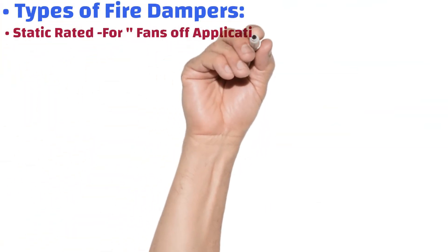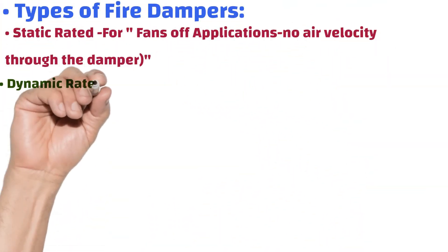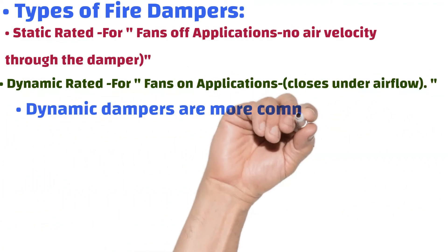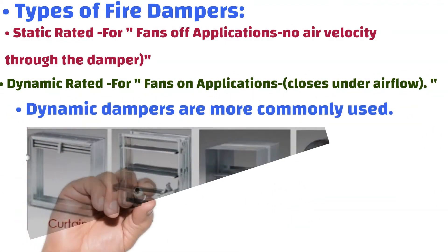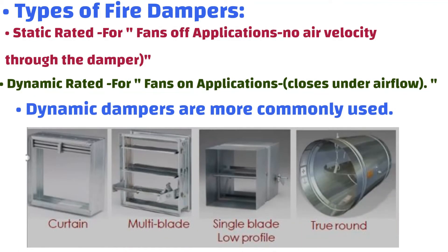Types of fire dampers based on usage are divided into two: static fire dampers and dynamic fire dampers. Static fire dampers are designed to cut off airflow when a fire strikes — triggered by a building's fire system, which automatically shuts off the HVAC system. Dynamic fire dampers are used for applications where the HVAC blower may continue to run during an alarm and are rated to close with and/or against moving air.